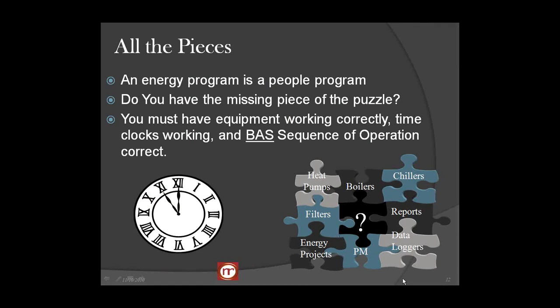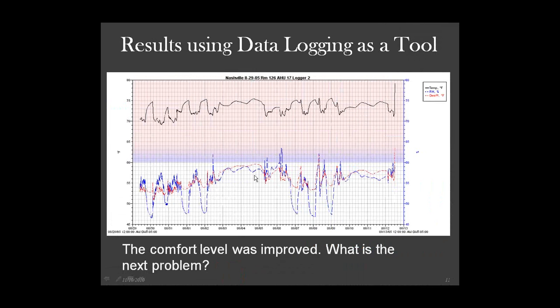Now, some of the things you've got to know, it is definitely a people... Charles? Yes. But before we get too far away from the data loggers, we had a question on how and where the data loggers were installed. Okay, that's a great question. Typically, data loggers need to be installed near the thermostat or the return vent. If you place them near a discharge or supply vent, then if you're heating, you're going to get excessive hot air, or if you're cooling, you're going to get excessive cold air. So locate the thermostat, and typically that's probably by the door, and you're going to find the return grill probably by the door. Somewhere there that it can sense the room would be a great opportunity for you.